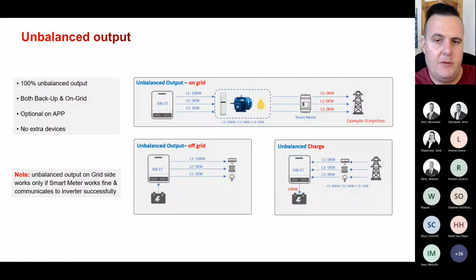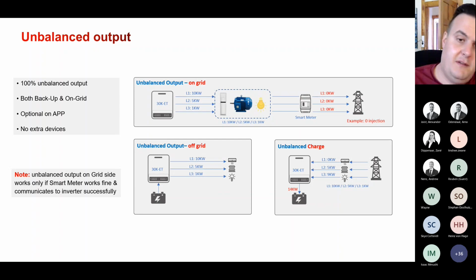Then the unbalanced output, which we mentioned. The unbalanced output is a functionality used especially for zero export. For a lot of places where you're not allowed to export to the grid, this feature was unique to GoodWe. We were the first to release this feature. With a device, you'll see the on-grid load, so this is not talking about backup, the backup side is always going to be unbalanced. But on the on-grid side, when we have zero export enabled and we are consuming, if you have some loads on your backup, and some loads on-grid that you don't need to run off batteries when the grid fails, those loads will also be compensated by the PV and the batteries when the grid is available.